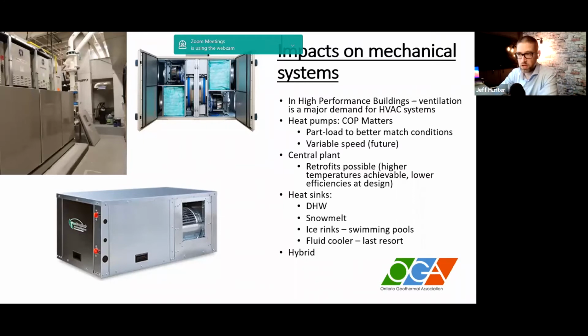But caution here, because controls and commissioning in any case is absolutely important. When introducing a conventional system hybrid into a geothermal system, we don't want to be overheating the loop. You could have a boiler heating up a loop without knowing about it, or a fluid cooler extracting too much energy from a loop. So control systems and commissioning become very, very important in those situations.